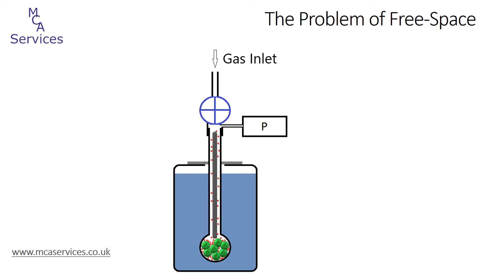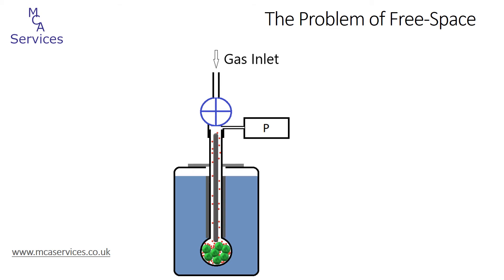Using Micromeritics instruments also means that we can insert isothermal jackets. These sit around the outside of the analysis tube and act as a wick, maintaining a constant cryogen level. This means that thermal stability and accuracy of the free space measurement are constant throughout the analysis, even as the level of liquid nitrogen naturally falls over time due to evaporation. Improvements in instrumentation mean that the lower limit at which nitrogen can be confidently used for surface area measurement has fallen dramatically. A few decades ago surface areas below 10 square meters per gram were considered difficult to measure; now we can comfortably and confidently measure below one square meter per gram with nitrogen.